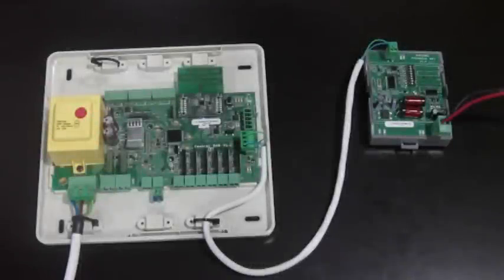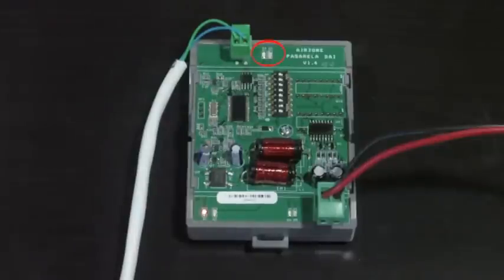Once connections and microswitch configuration is accomplished, power simultaneously the zoning system and AC unit. The correct working of the gateway can be checked through the indication LEDs: communication with the main controller LED should be blinking on any communication, communication with the AC unit LED should be blinking on any communication, power supply LED should be fixed at any time the gateway is power supplied, and activity LED should be blinking anytime the gateway is power supplied.